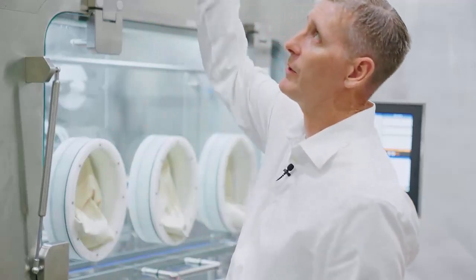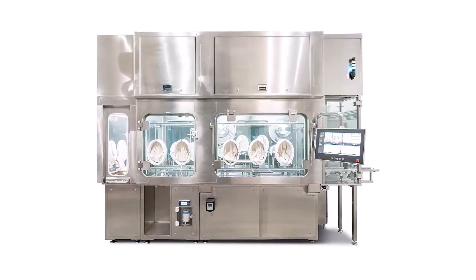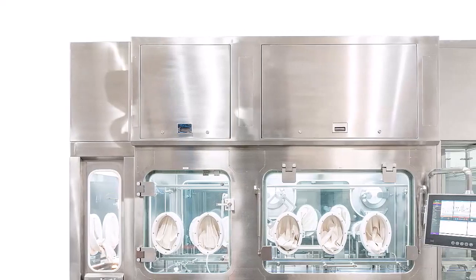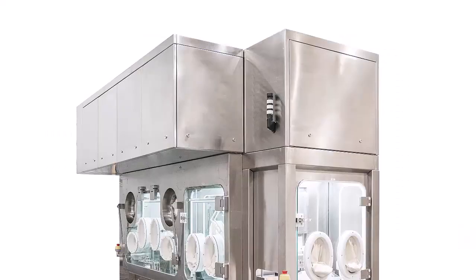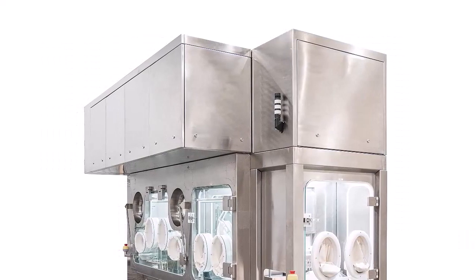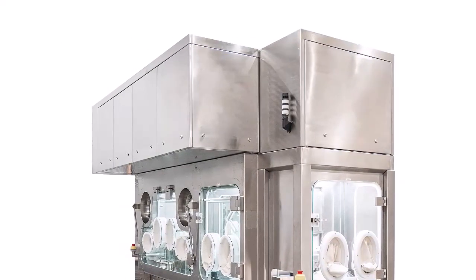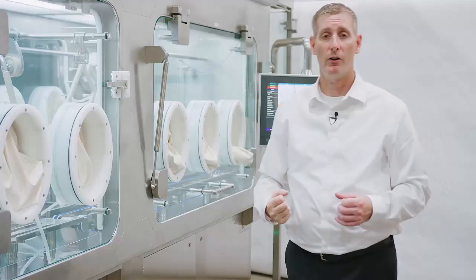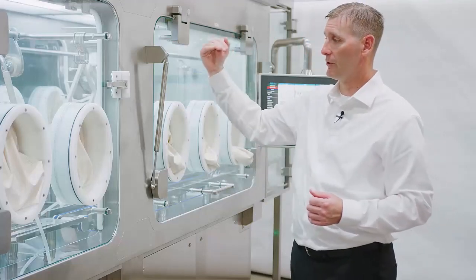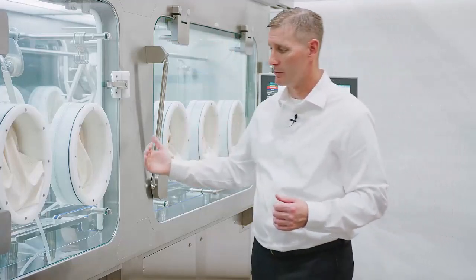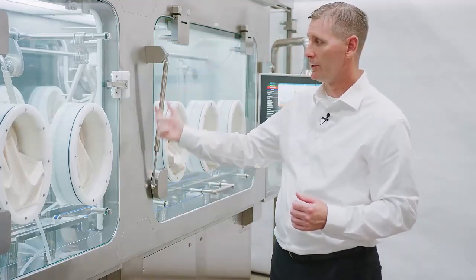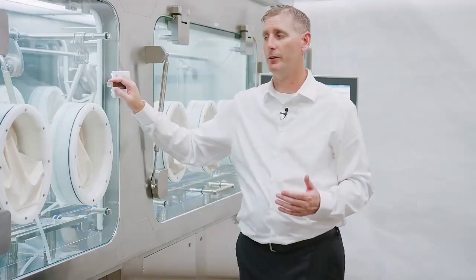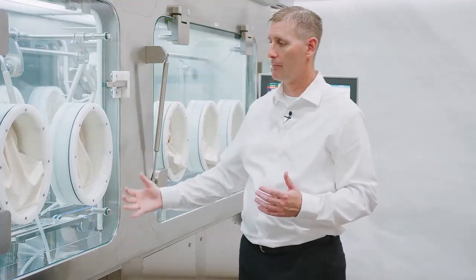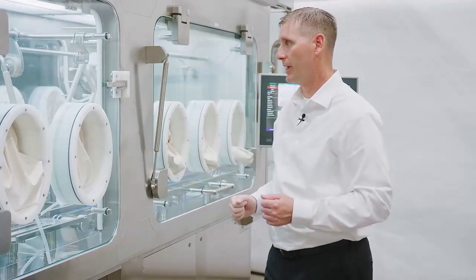Isolators are known to be really tall, but we were able to design the air handlers to marry up to the modular clean room panels above without interfering with the interstitial air, things like ductwork, fire sprinklers, and other interferences in play. The air handler takes air from the room, HEPA filters it, and recycles or recirculates the air through our double wall construction, pulling it through the double panes of glass and back up to the air handler.